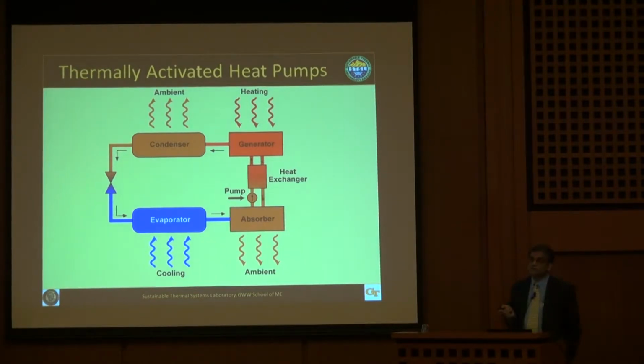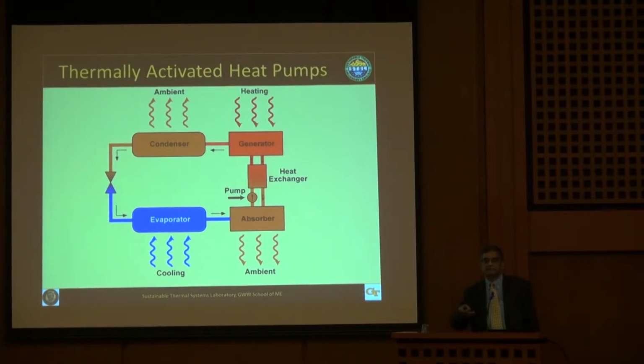Instead, you can use heat to drive this system, perhaps from solar, perhaps from some waste heat, and instead of running electricity, you boil a refrigerant out of a solution. This part of the cycle remains the same, and when this evaporated refrigerant does its cooling, it mixes back into the solution so that now you need to pump liquid rather than compress vapor. Pumping liquid takes maybe a hundredth of the energy needed to compress vapor.